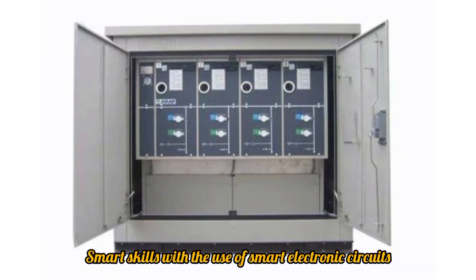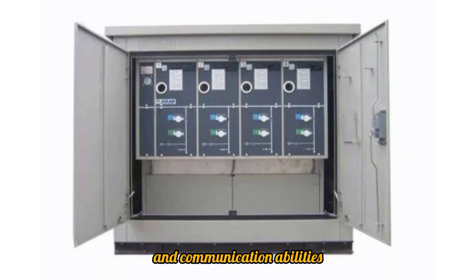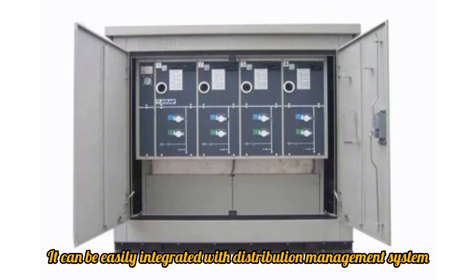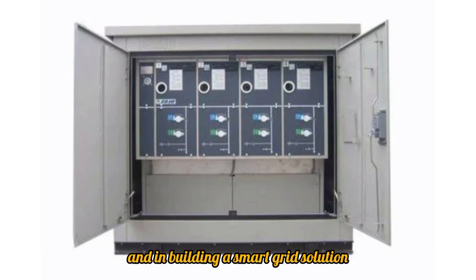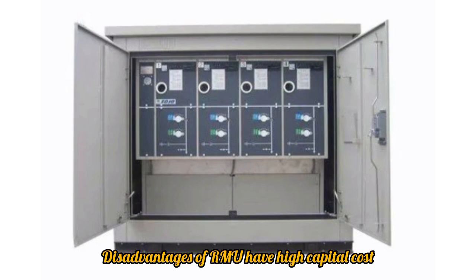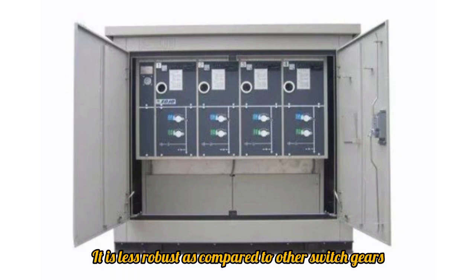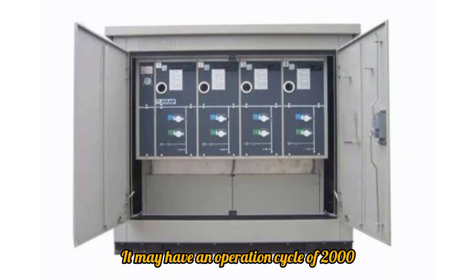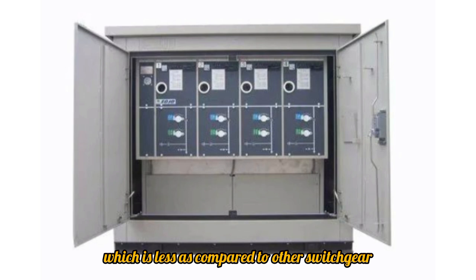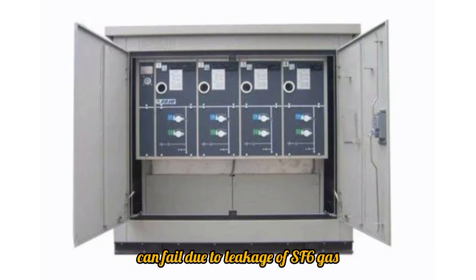Smart skills. With the use of smart electronic circuits and communication abilities, it can be easily integrated with a distribution management system and in building a smart grid solution. Disadvantages of RMU: it has high capital cost. It is less robust as compared to other switchgears. It may have an operation cycle of 2000, which is less as compared to other switchgear, and can fail due to leakage of SF6 gas and moisture entry.